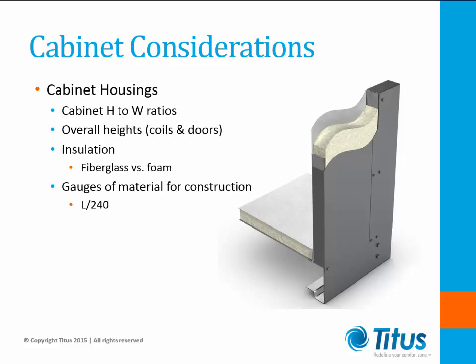More recently, many manufacturers have moved to injection foam cabinet construction, which is extremely rigid. Injected foam insulation with no through metal connections, known as thermal bridging, is available from a variety of manufacturers and generally has a better thermal and acoustical performance than fiberglass insulation. A disadvantage of using fiberglass insulation is having to use heavier gauge sheet metal for structural integrity. Lighter gauge material with foam insulation can meet and or exceed fiberglass insulated walls with heavier gauge metal designs.